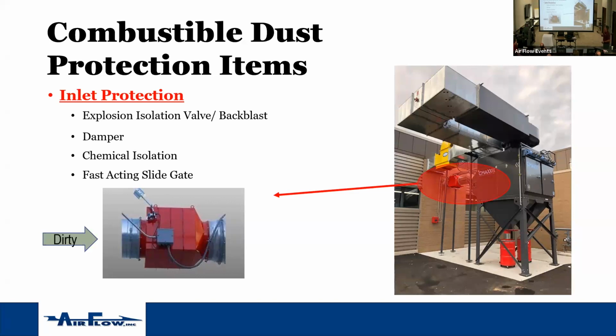So that will go in this picture. It's kind of hard to see. In this picture, it's located right here on the inlet. Your dirty air comes in, as your dirty air is coming through, this is just a weighted damper, similar to a backdraft damper technology. The air comes through here, the damper will open, dirty air will come through here. As that explosion occurs, this is going to close.